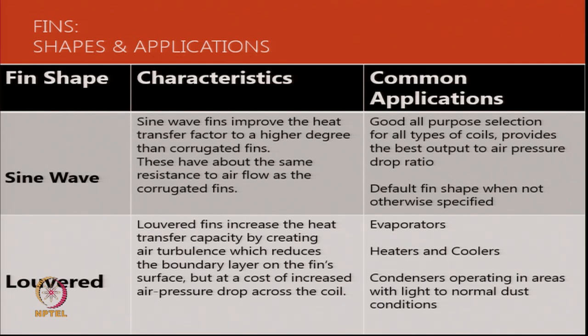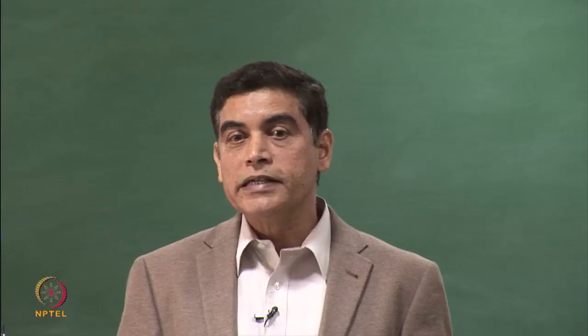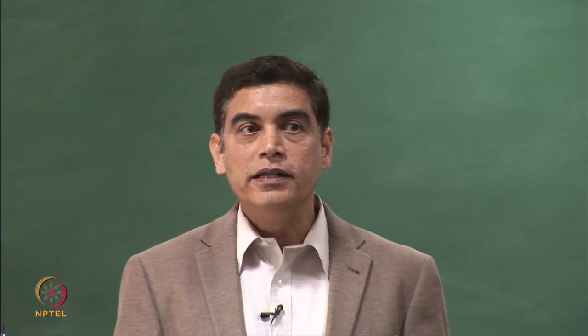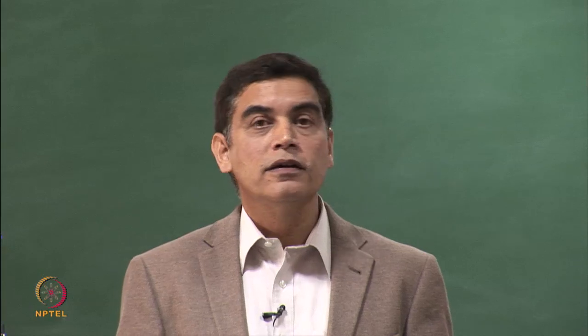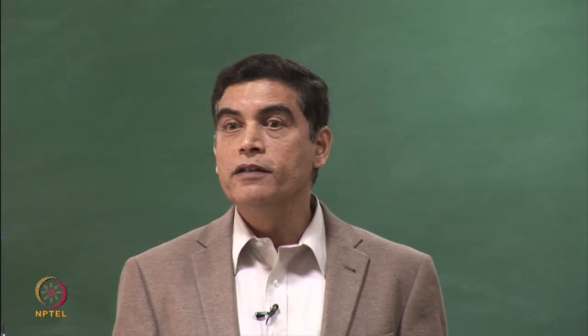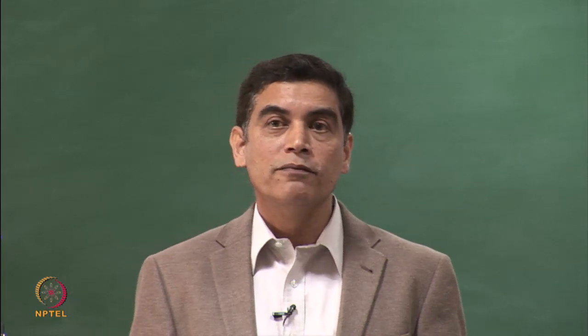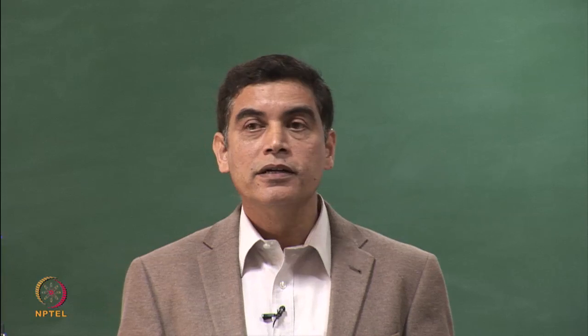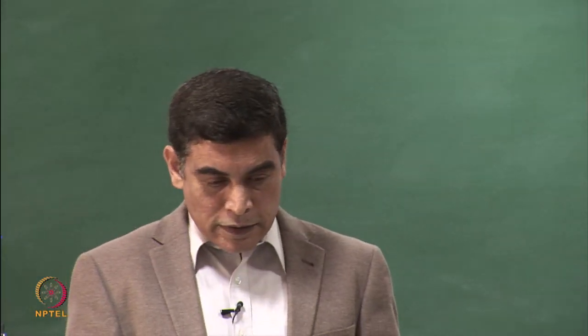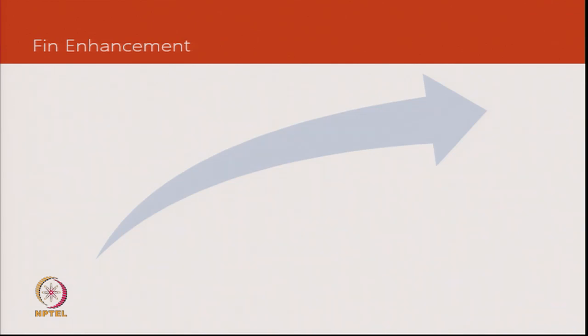The louvered, we have talked, is the highest turbulence generating fin, and it is also offering the highest rate of heat transfer on the air side, and it comes with a penalty, which is higher pressure drop. But they have been used so much that the trade-off has been accepted. So when you go to a fin density as high as 18 fins per inch and a louvered fin for evaporators, they have been helping manufacturers build compact indoor units that have also been acceptable to the market in terms of cost and performance. If you look at the summary, we have the basic plain fin, and then we have the corrugated fin, the sine wave fin, and on top for performance is the louvered fin.